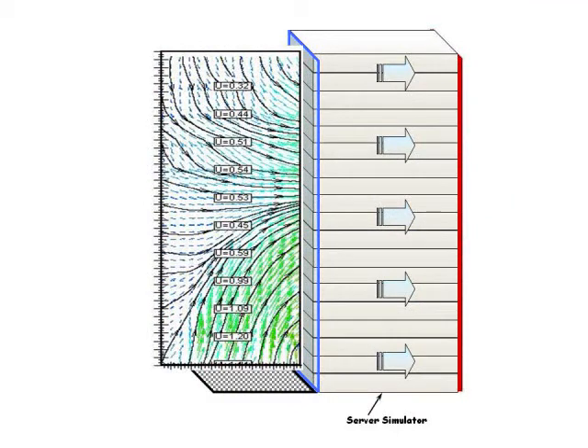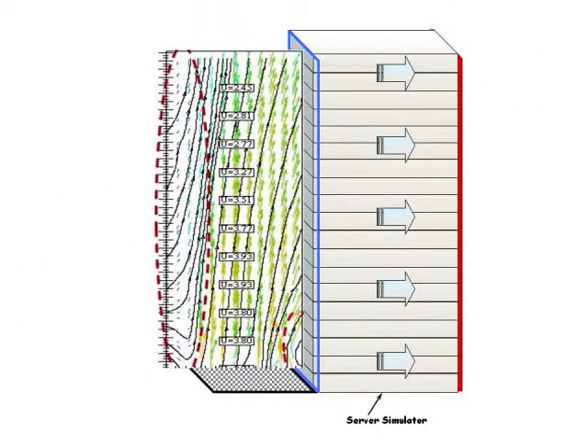In case 2, we have 20% of the air flow rate requirement of rack coming out of the tile. In this case, we see that only half of the servers get the cold air coming out of the perforated tile, and top half of the server are getting hot air recirculated in the room. In case 3, as we increase the air flow rate through tile to 60% of rack air requirement, we see that some of the air is directly shooting out from the top of the aisle. We also see a recirculated region on the bottom of the rack. So these studies show that PIV system is very useful in predicting as well as evaluating the flow field inside the data center and coming out with strategies which are useful in thermal management of data center.